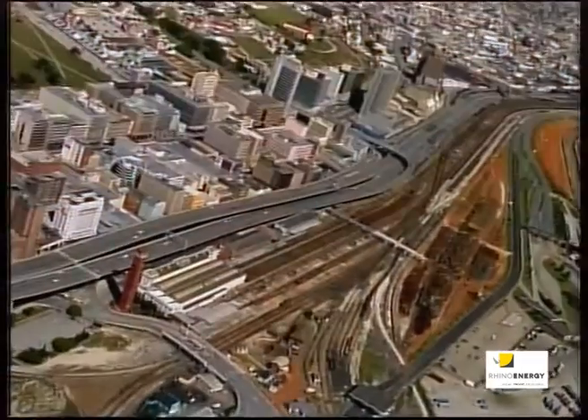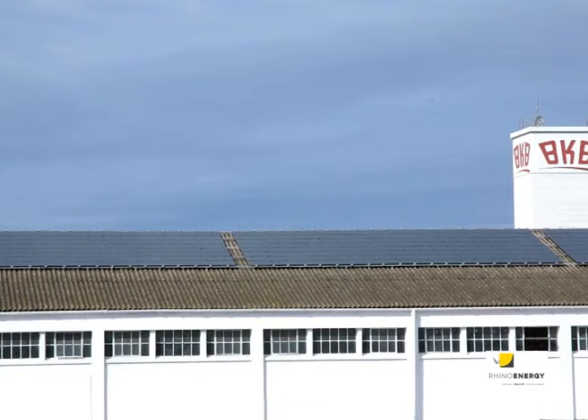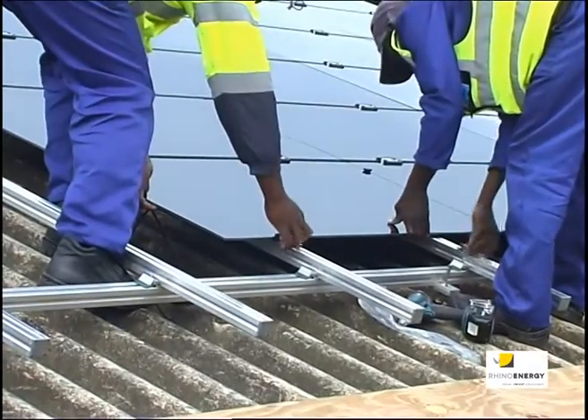The system harnesses solar radiation, which is of exceptional value here in the Port Elizabeth region, and converts it into electrical energy. The key metric is kilowatt hours generated. Using a simulation model — to be referenced against actual performance over the coming years — the system will generate approximately 750 megawatt hours, or 750,000 kilowatt hours. To contextualise that, it's the equivalent of 750,000 kettles running for one hour. On a daily and weekly basis, the solar system should displace between 25 and 30 percent of the building's current energy consumption.